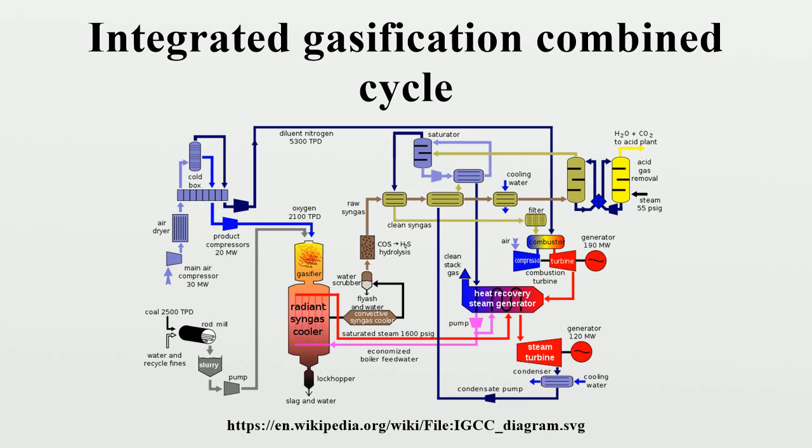First, the project was initially shut down because of corrosion in the slurry pipeline that fed slurried coal from the rail cars into the gasifier. A new coating for the pipe was developed. Second, the thermocouple was replaced in less than 2 years, an indication that the gasifier had problems with a variety of feedstocks, from bituminous to subbituminous coal. The gasifier was designed to also handle lower-rank lignites.